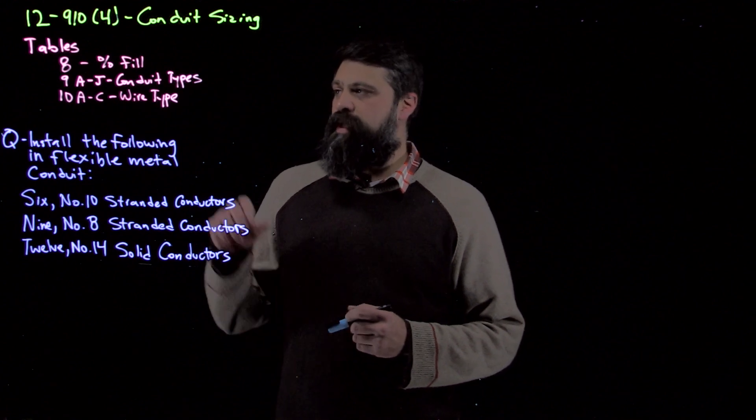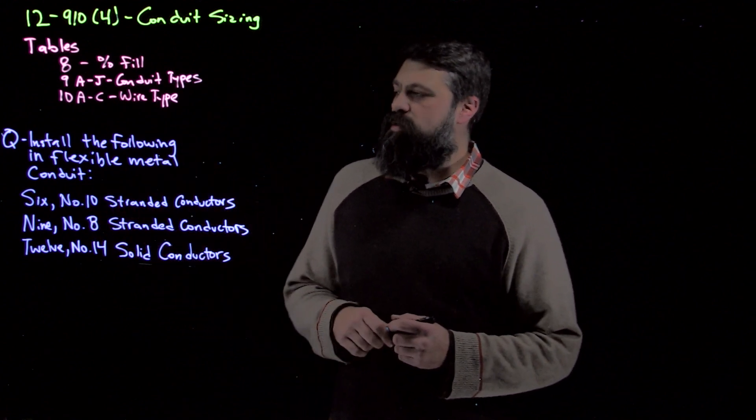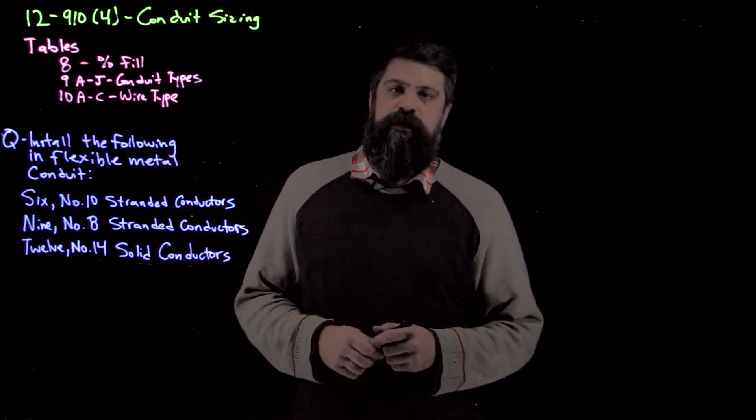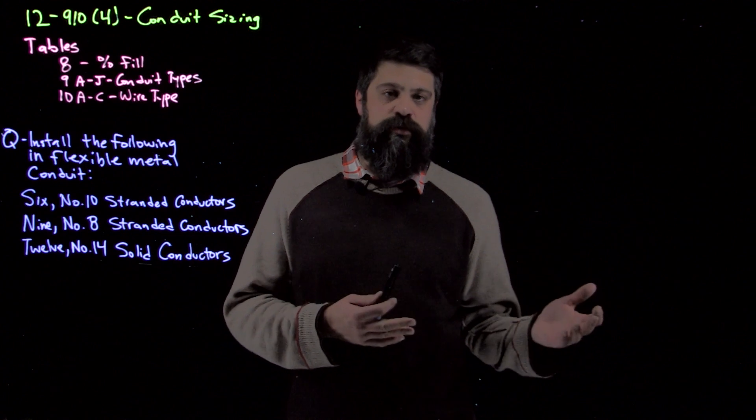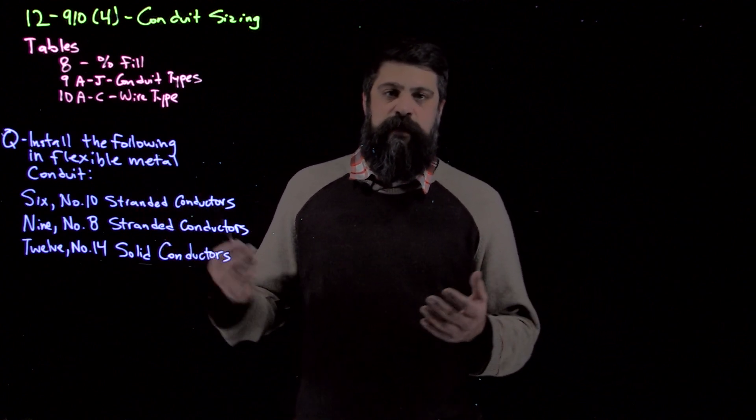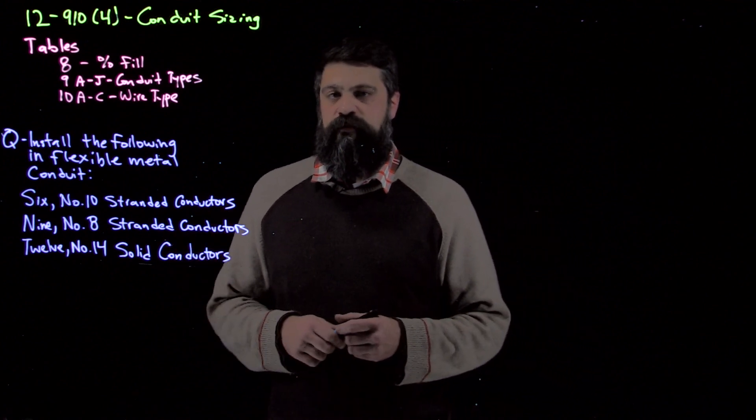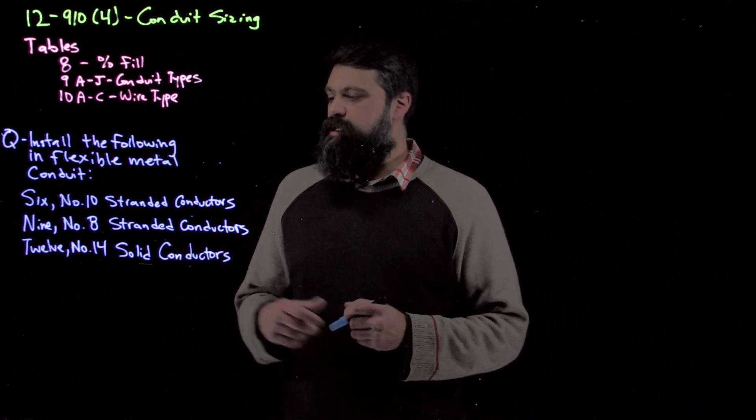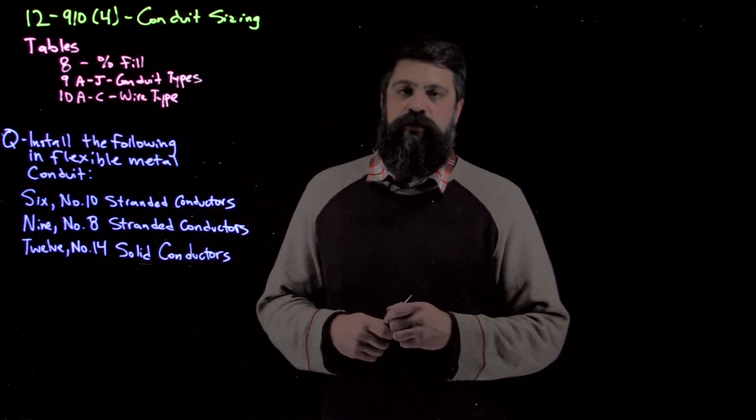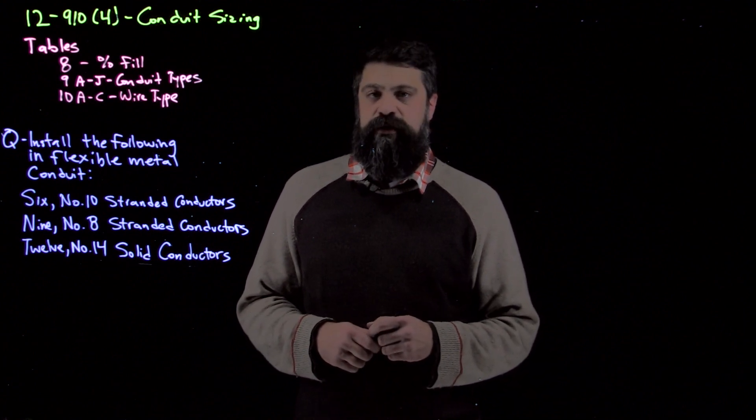We're going to size some conduit based on having different types of wire inside of the conduit. So that's going to take me through these tables. Table 8 gives me a percentage fill. Tables 9A through J shows me some different conduit types, as well as tables 10A through C gives me a wire type. So I have stranded conductors and I have solid conductors that we're generally using for the examples that we've had so far. So in this question I have some stranded and I have some solid. Let's go through and take a look at what we can do to actually install these in some conduit.